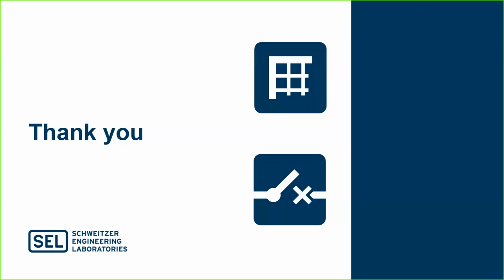Yeah, no, it does. So when you have an automation system like FLISR out there, its job is to lengthen feeders in order to pick up load that would otherwise be left de-energized after a fault. Those feeders can get relatively long, especially if the fault was in the breaker zone or on the high side of the breaker in the substation somewhere. So the way I'm interpreting that question is, the longer a feeder gets, the lower the voltage at the end of that feeder becomes. Now, you could do something like line drop compensation in a 2431 that would help with that.